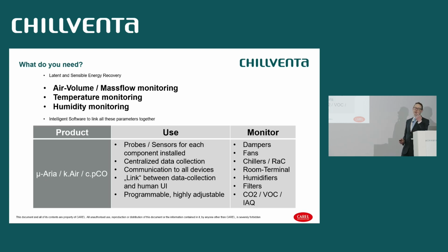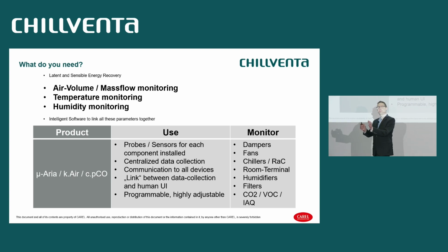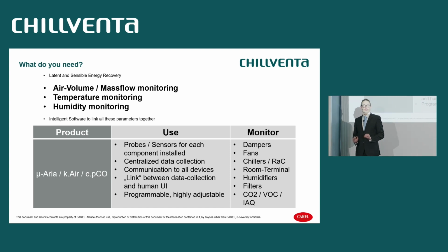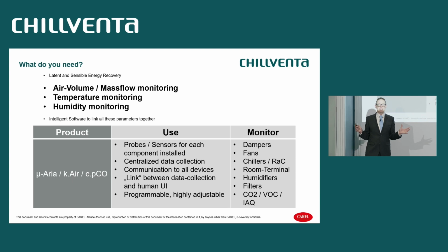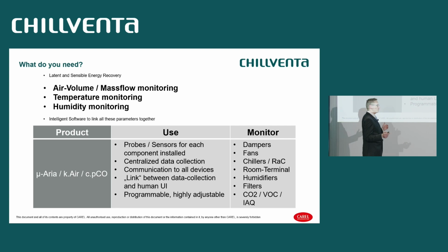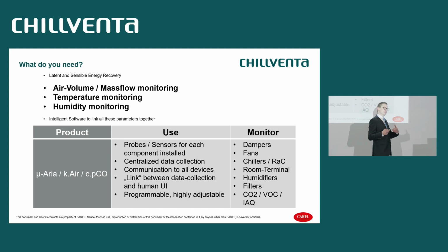But this is just the energy recovery part. You don't know how much energy it saves. You don't know how long you need to go on top until you have your target. Because it is a black box. You need to take a look inside. So you need controls. You need controls for dampers. You need controls for air volume. You need controls for bypasses. You need controls for temperature, for humidity.